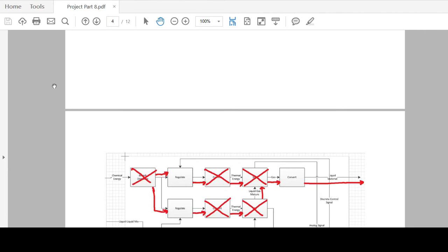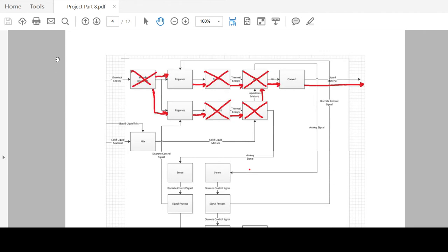Next, I'm assessing the failure of the branch distribution of the natural gas that powers the two incinerators. Essentially, if this valve that splits the natural gas supply into two were to clog or fail, then both incinerators fail, because they can't convert energy that doesn't exist, the liquid is not boiled, and dangerous pathogens could possibly be dumped into the sewer system. This means that this failure propagates in a critical way, and the system cannot do its job.